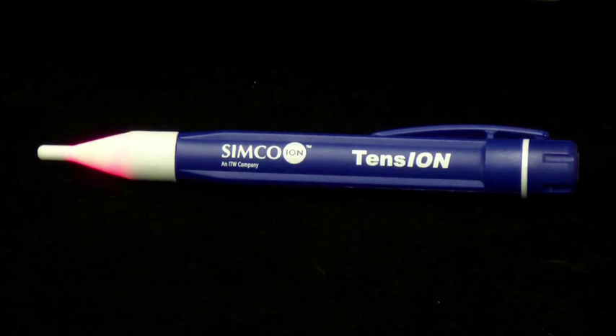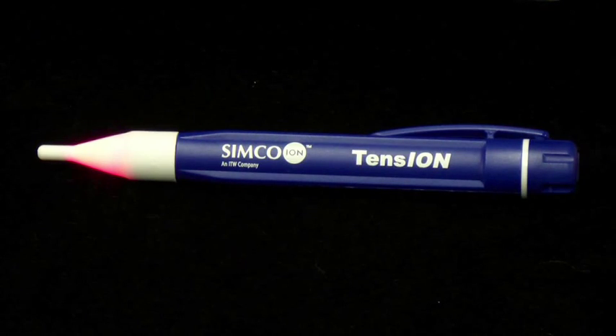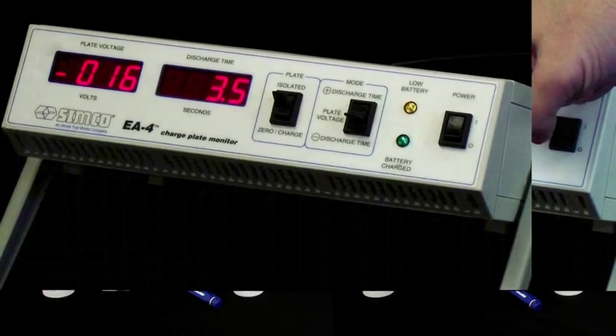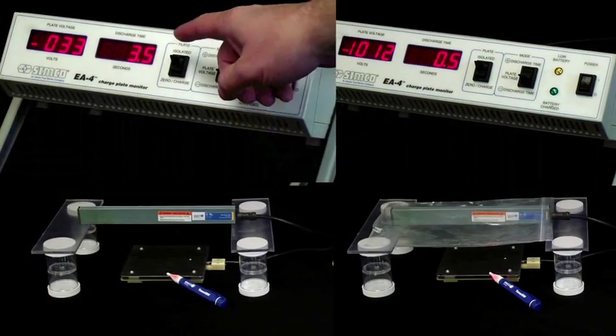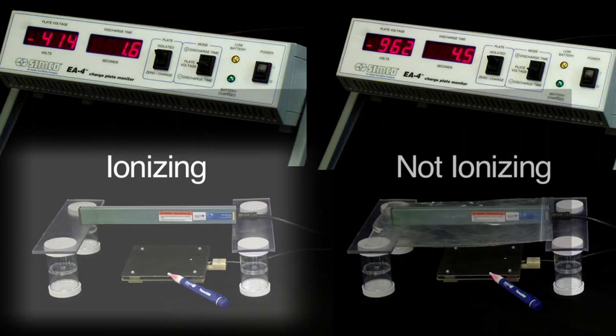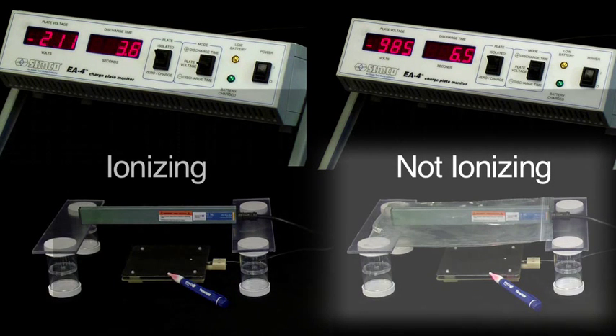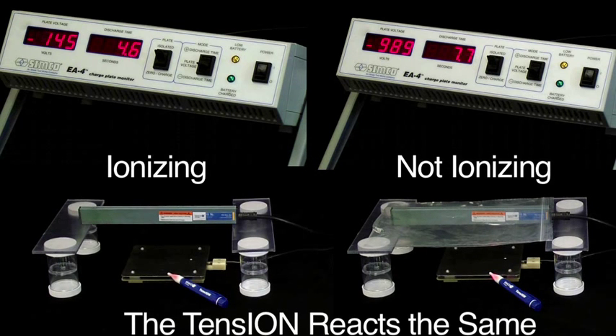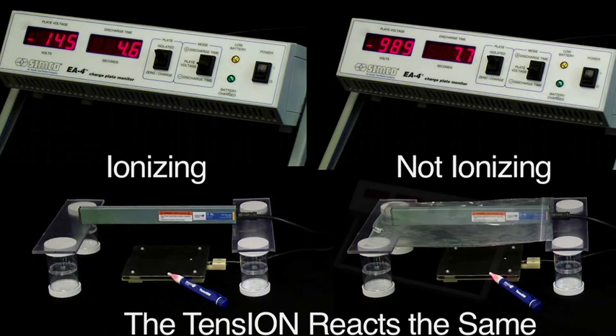As we've shown, the TensION reacts to voltage only, not ionization. We prove this by putting it below a static bar while creating ionization, then we put it under the same bar but blocked ionization. In both instances, it reacts the same, proving that the ionization created by the static bar has no effect on the voltage detector.